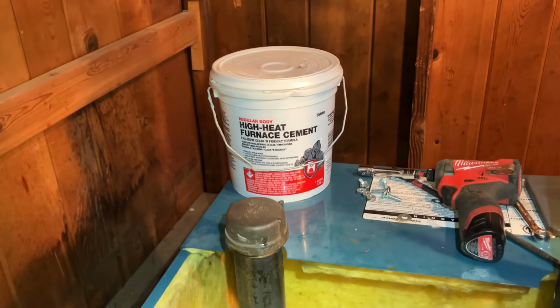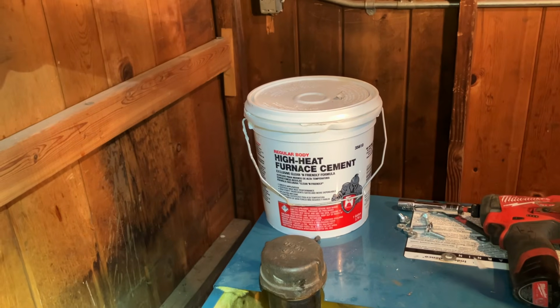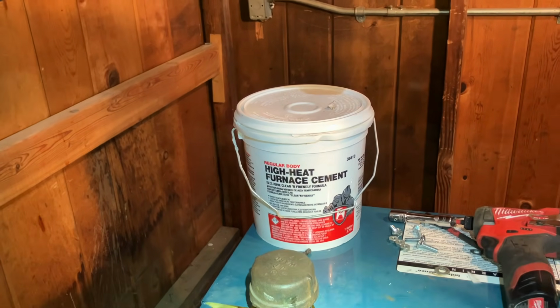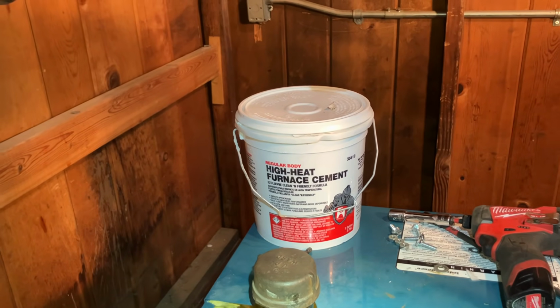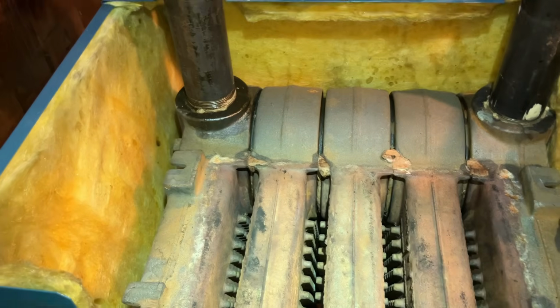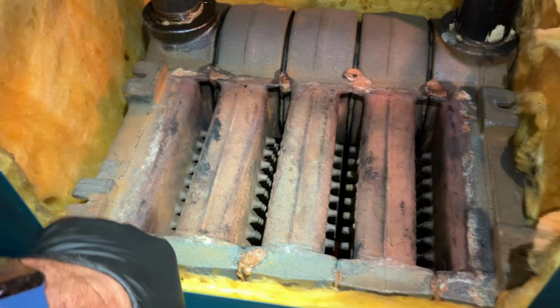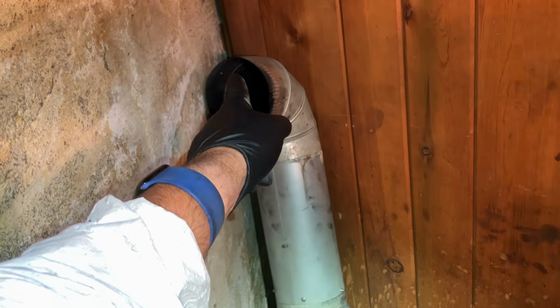I got some furnace cement. It's quite cold outside, so it's been sitting inside since I got here for about an hour and 45 minutes already. No, 2 hours now. So even though there's no heat in the house, it's still like 65, 60 degrees in this basement. Better than being in the truck and being frozen at 30. We're going to apply some furnace cement around the perimeter here, and I'm going to place the internal draft hood back in. Now I did vacuum it up and brush it clean as best I could, so I'm not going to be putting anything back dirty. That is a little bit more of a challenge, but we'll cross that bridge when we get to it.